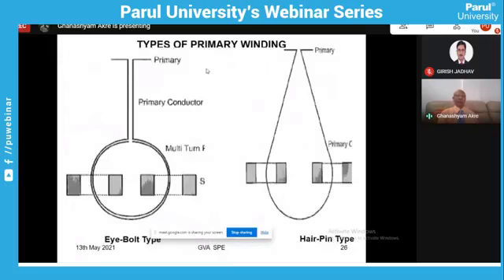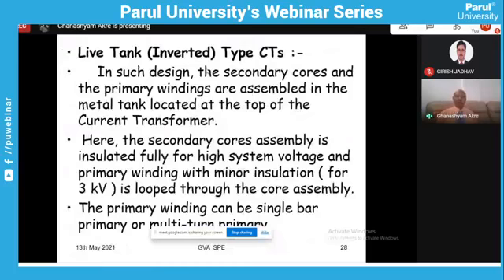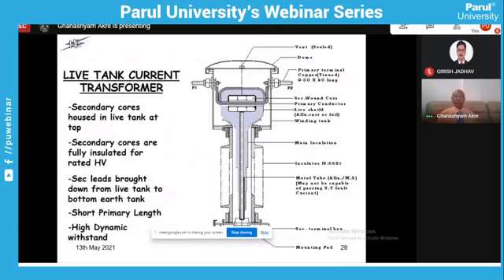If you go for the live tank design, what happens in the live tank is this. Here you see the primary is at the top. This is P1 and it takes a few turns across the core. And the core also is at the top. Now this core is connected through these leads to the secondary terminals, which are at earth potential. That means the core here is at earth potential, while the primary here is at line potential.